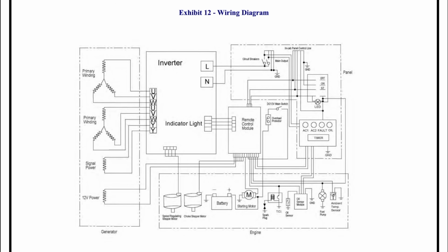This one's even simpler because it's an inverter generator, and if you look at the wiring diagram for this inverter, you can see there's only 1 line coming off the inverter anyway, and it just gets arbitrarily split to the 2 lines. So basically it's being split and rejoined. It's really no different as far as the inverter, where the energy is actually created in that generator, is concerned, to create this jumper, this bridge between line 1 and line 2 out of the generator.